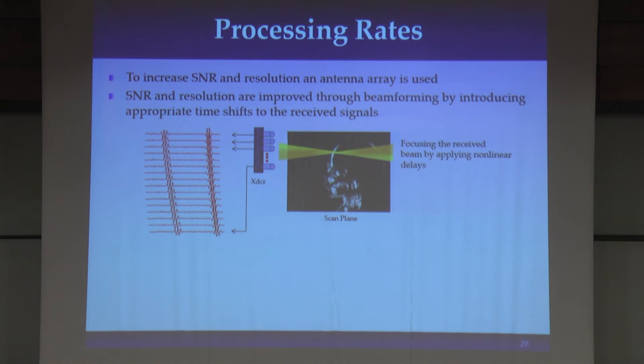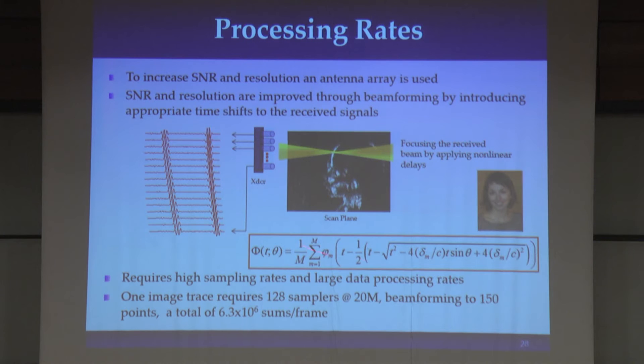To overcome these obstacles, in practice ultrasound uses an antenna array within the probe — typically between 128 and 256 elements — and we receive the signal in each one of these elements. In each element, you're receiving a time-distorted version of the same signal where this time distortion is determined by the geometry, which is something that you know in advance. Once you have all these many signals, you can combine them in a process called beamforming — a nonlinear combination — and once you perform this combination, you're basically both increasing the SNR and increasing the resolution. The difficulty, though, is that you're not going to do this in the analog domain, so you sample the signal and then do it digitally.